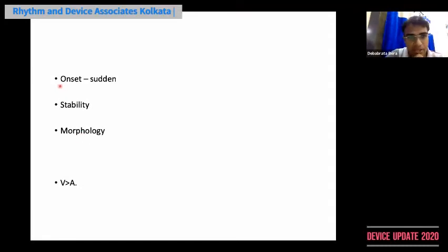But let us concentrate on what onset is, what does it mean? If there is a rapid onset of tachycardia, the ICD will consider it as a VT. Although it can be atrial tachycardia, atrial fibrillation, anything can start rapidly. But for the ICD, if it starts rapidly and suddenly, it generally thinks it is a VT. What about stability? If there is a slow onset, the device will call it an SVT. It will consider the gradual onset tachycardia as a sinus tachycardia. Although in rare situations, you can have gradually increasing tachycardia of VT.